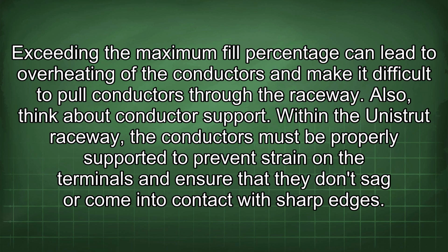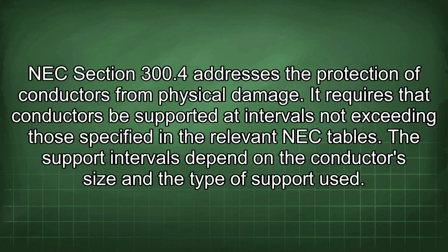Within the Unistrut raceway, the conductors must be properly supported to prevent strain on the terminals and ensure that they don't sag or come into contact with sharp edges. NEC Section 300.4 addresses the protection of conductors from physical damage. It requires that conductors be supported at intervals not exceeding those specified in the relevant NEC tables. The support intervals depend on the conductor's size and the type of support used.